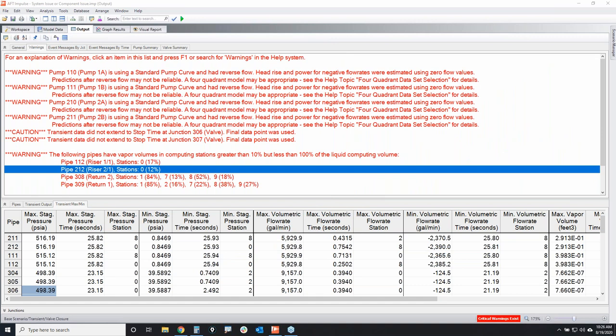There's more to it. You've got to dig deeper. If you have cavitation going on, you can potentially have higher pressure spikes than what this equation will predict. This can also be if you have line packs. So if you're deadheading against a closed valve, your pressure can increase over time. And that's a line pack situation where your pressure can be higher, again, than what the Joukowsky equation will tell you. So you got to look at this deeper.